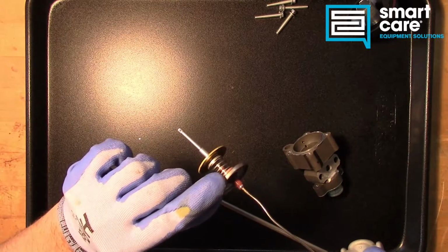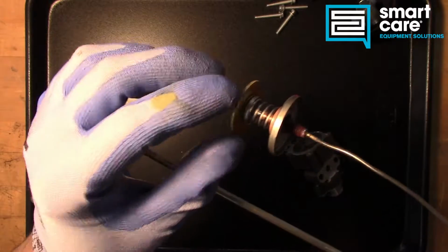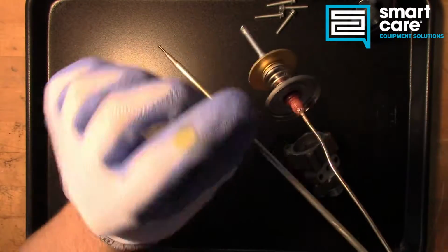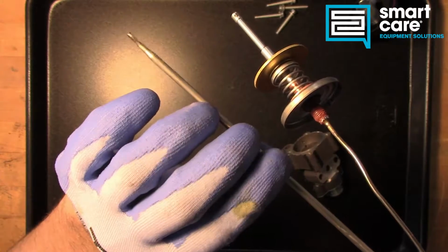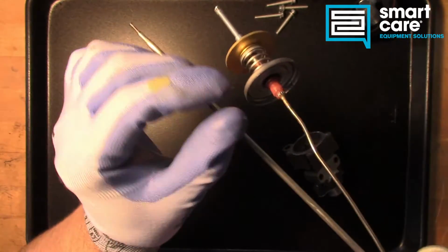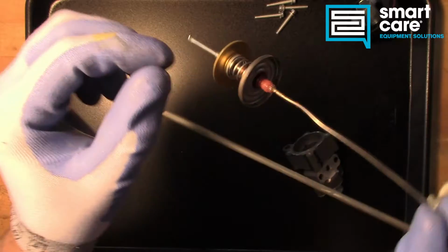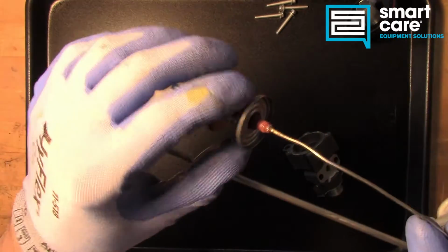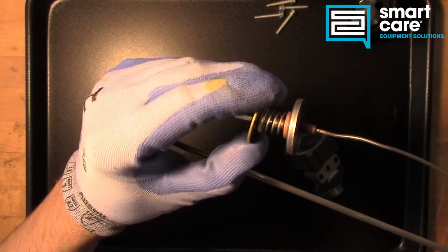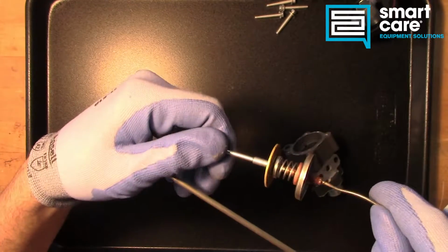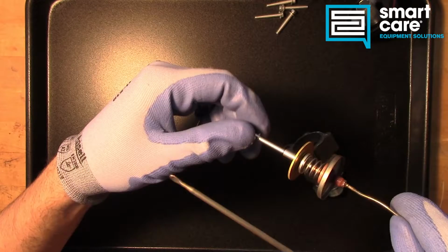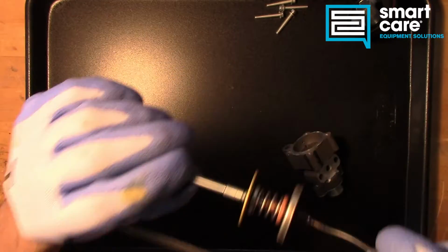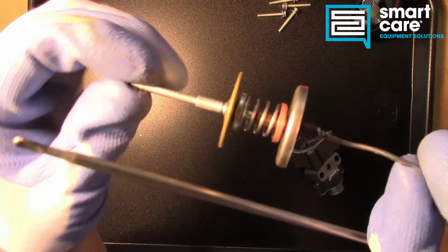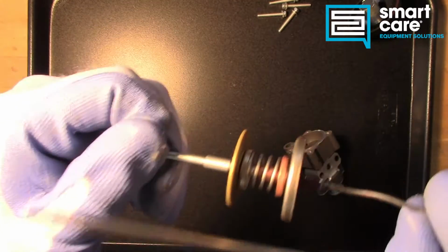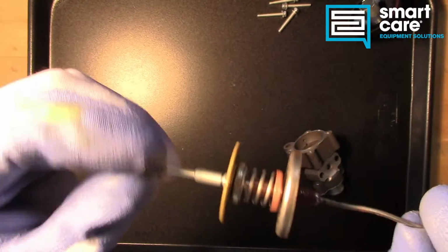So this back here, it looks like one piece, but it's actually two, and it's bonded together so it makes a bellows. And as the fluid in here heats up, it's expanding, and that makes this bellows grow. It doesn't grow a lot, but it puts more pressure on the spring system here. And it looks like as this T-handle is turned, it's threading in and out of this threaded portion inside here. So it's changing the amount of pressure on that spring as we turn this in and out.